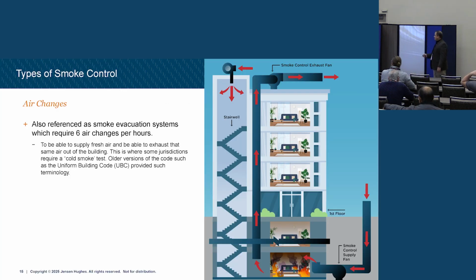Okay, so air changes can be used anywhere in a building. This is not as common, but basically I'm using forced supply air and exhaust air, and I am trying to dilute the smoke out of that space. I'm not a super big fan of this one because it can also feed your fire, but it is used.